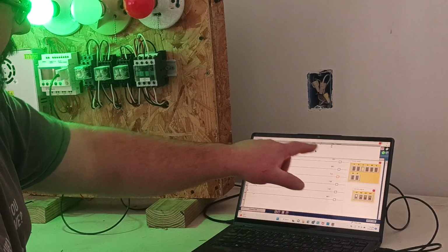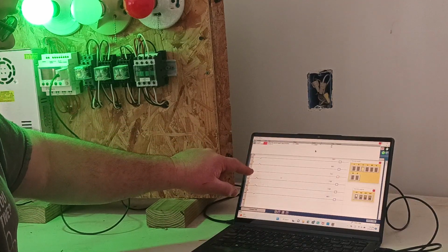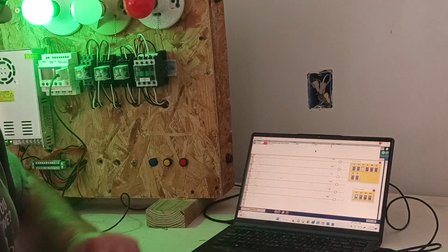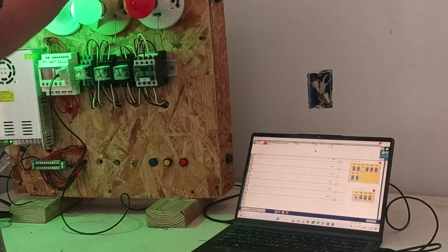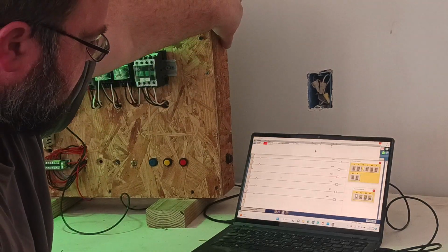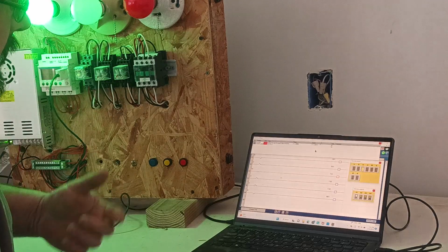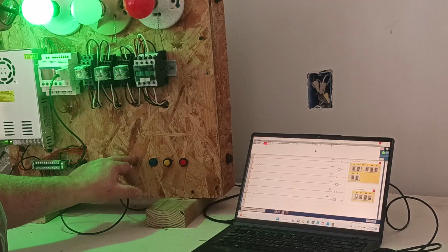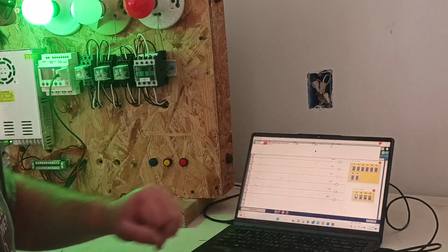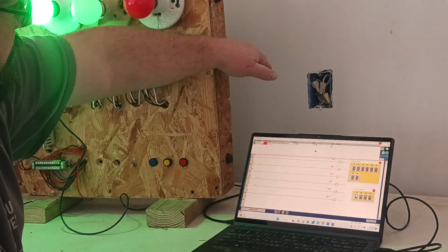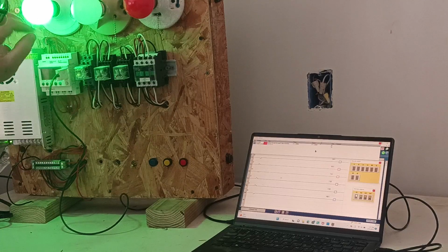So as you can see, once I hit my preset value of 6, my counter contact closes, and now I have my final output. And as you can see, I can count higher than 6. Right now I'm at 10, but nothing else happens because I've already hit 6. So I can decrease, I can change this, and now I'm on my decrease. My value is 10, so we'll go 9, 8, 7, and of course my green light's still on because I'm still above 6. 6, my green light is still on.